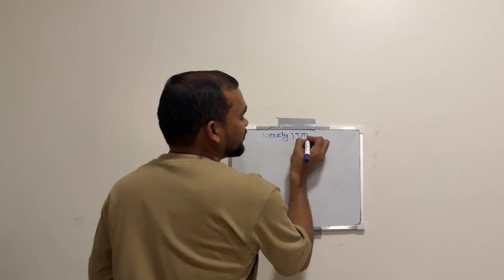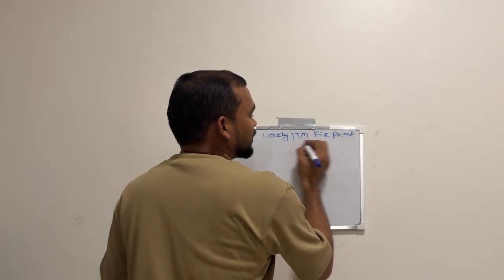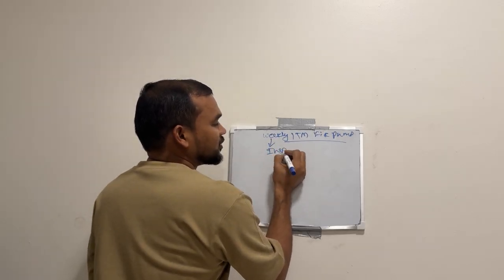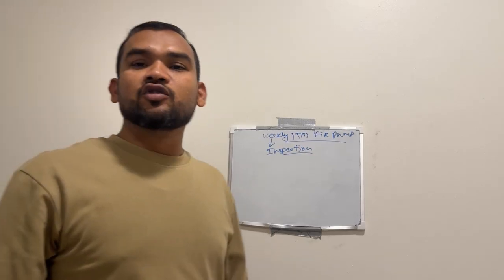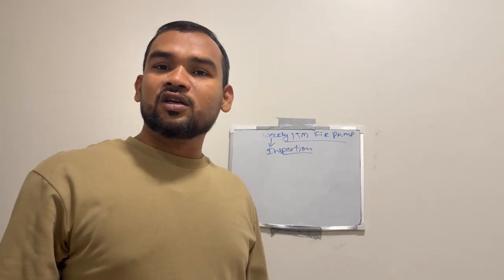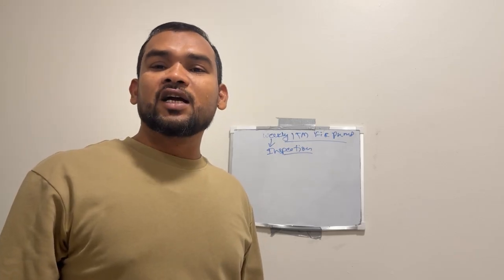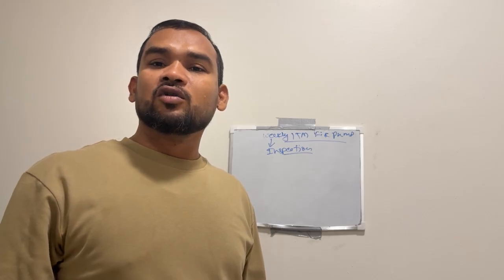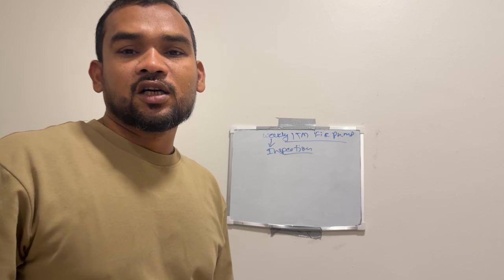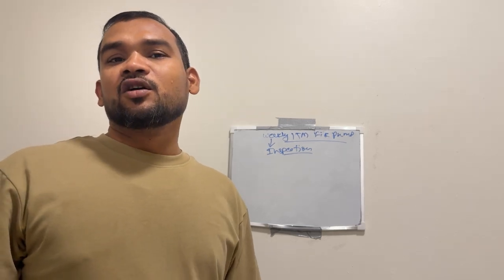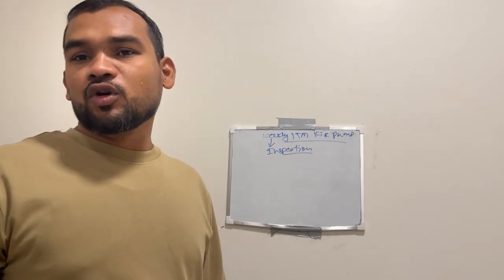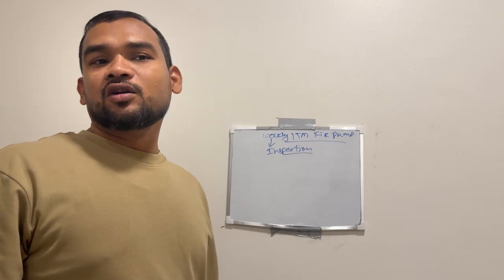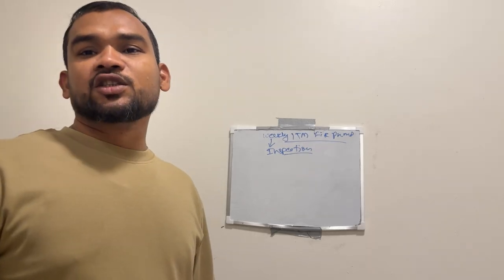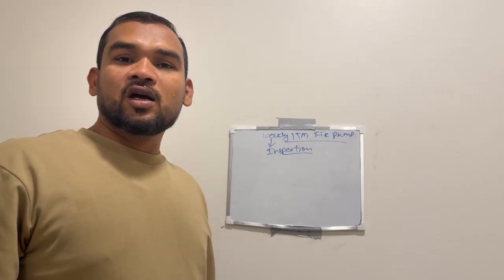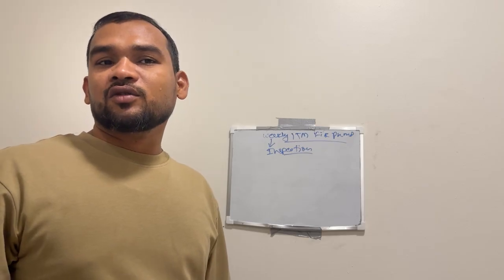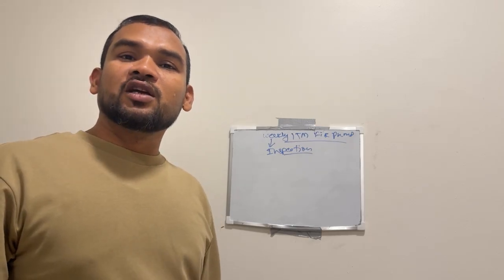Weekly ITM fire pump. What we have to check? What is visual inspection? We are doing a visual inspection of the fire pump to check everything is in normal condition. Like in the pump house, we have to verify the louvers are unobstructed and free to operate or not. We have to check the temperature of the fire pump room is in an acceptable range or not. We have to also check the coupling guards are properly installed and securely in place or not. We have to also check in the pump system that the pump suction and discharge pressures are okay and the valves are fully open. And we also inspect the fire pump piping to verify it is free from any leakage.